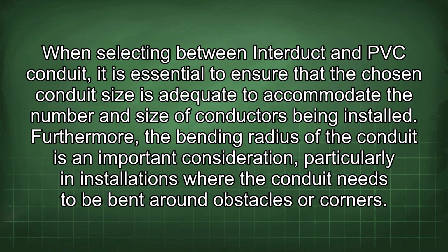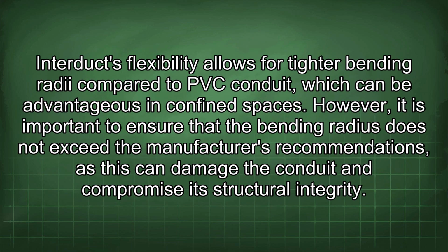Furthermore, the bending radius of the conduit is an important consideration, particularly in installations where the conduit needs to be bent around obstacles or corners. Interduct's flexibility allows for tighter bending radii compared to PVC conduit, which can be advantageous in confined spaces. However, it is important to ensure that the bending radius does not exceed the manufacturer's recommendations, as this can damage the conduit and compromise its structural integrity.